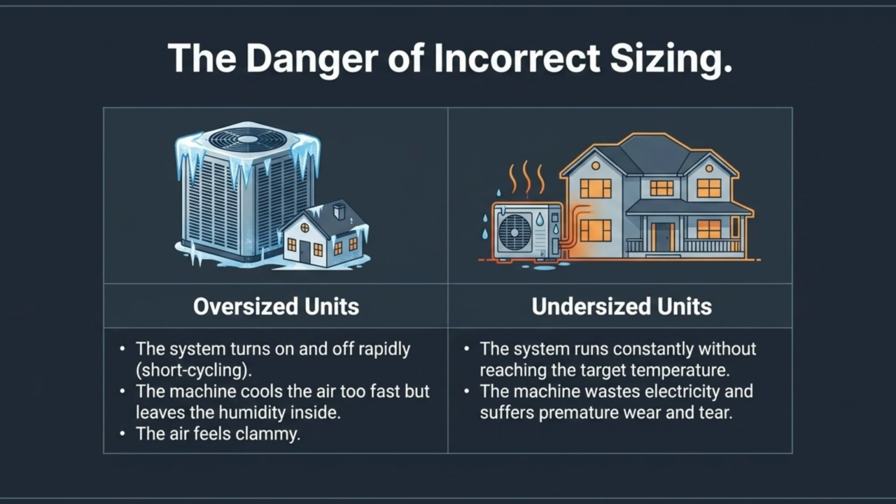Incorrect sizing presents dangers. Oversized units lead to short cycling, which cools the air but leaves humidity, making the air clammy. Undersized units run constantly without reaching the target temperature, wasting electricity and leading to premature wear.